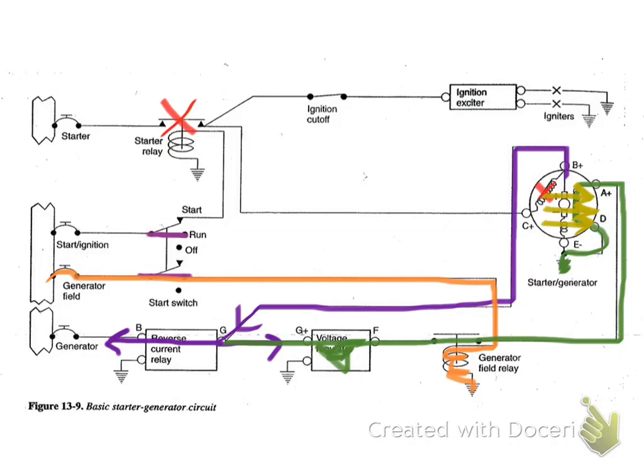That will control our lines of flux that are going across the armature. The voltage regulator is determining how much current is in the field. So if it raises the current in the field, the generator output will increase. Lowers the current in the field, generator output will decrease.